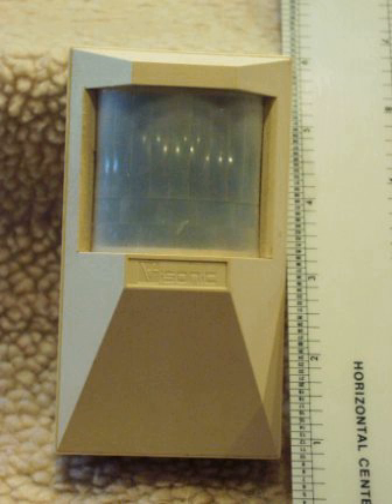The sensor converts the resulting change in the incoming infrared radiation into a change in the output voltage, and this triggers the detection. Objects of similar temperature but different surface characteristics may also have a different infrared emission pattern, and thus moving them with respect to the background may trigger the detector as well.